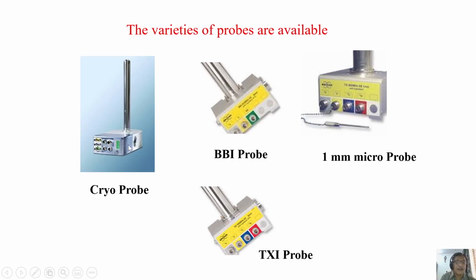So cryo probes are very advantageous, but remember, very, very expensive. A cryo probe for a particular spectrometer, let's say 700 or 800 megahertz, will cost almost as much as the spectrometer itself, or almost 2/3 the cost of a spectrometer. With the cost of a cryo probe, you can buy a complete low frequency NMR spectrometer of 300 or 400 megahertz. That is very expensive, but it has a lot of advantages. Because a lot of technology and research has gone into designing such a probe, it is very expensive.